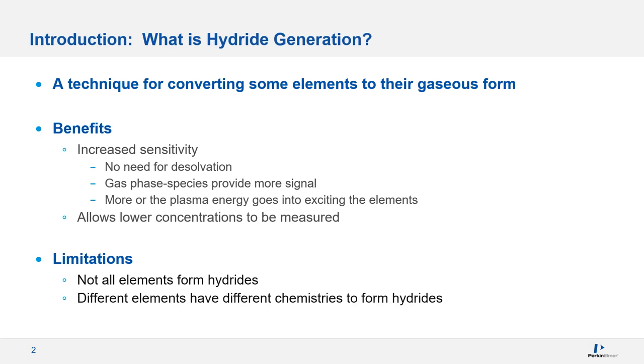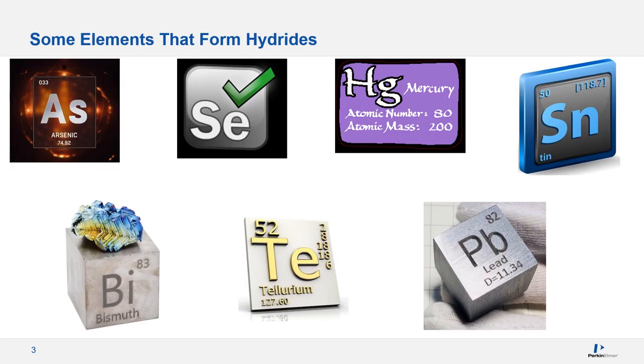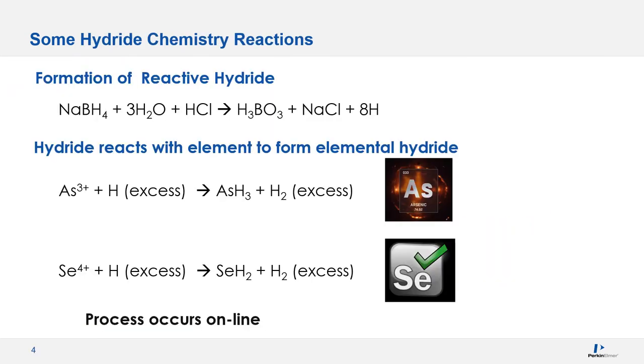Unfortunately, hydride generation does have limitations. First, not all elements form hydrides. Second, different elements have different chemistries to form hydrides, meaning different sample preparations are required. Several elements commonly form hydrides in ICP OES — arsenic and selenium are the most common requests for lower concentration measurements. Mercury, tin, bismuth, tellurium, and lead also form hydrides.